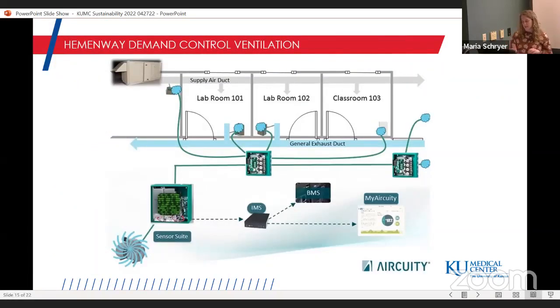In every laboratory room in Hemenway, there's a little plastic tube that runs back to a sensor suite. It continuously samples the air and measures it for volatile organic chemicals. If that sensor suite says the air is clean, we can reduce the airflow to that room, going from 10 to 15 air changes per hour down to 4 or 5, cutting it in half or more. Any airflow you can reduce lowers how much heating and cooling you need.